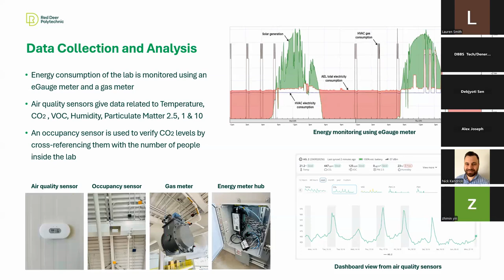One important fun fact: if you reduce the speed of the fan in the HVAC - for example, making your ventilation half, so the fan operates at half speed - you save way more power in electricity usage, because based on fan curves, energy is proportional to the cube of the fan speed. It's a cubic relationship, so you end up saving way more energy. When we calculate this, we get very good energy savings from this building - if done right and everything is optimized, we have a theoretical value of around 87% of the building's energy that we can save.